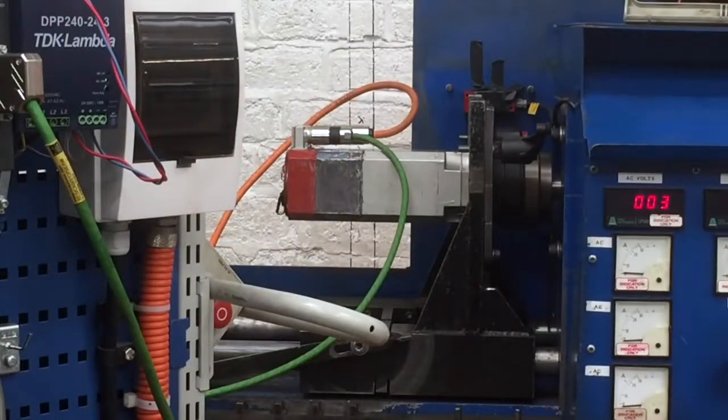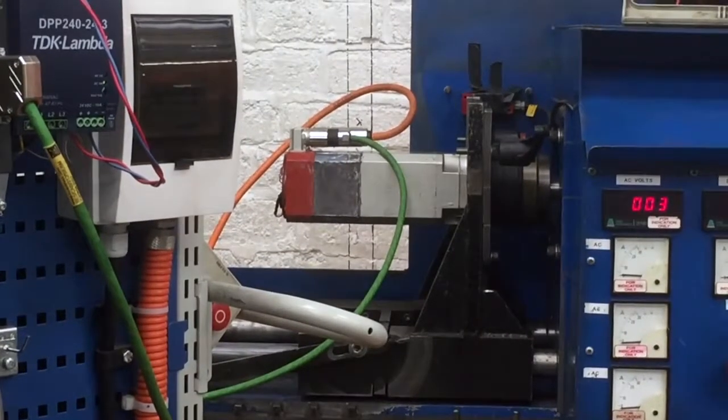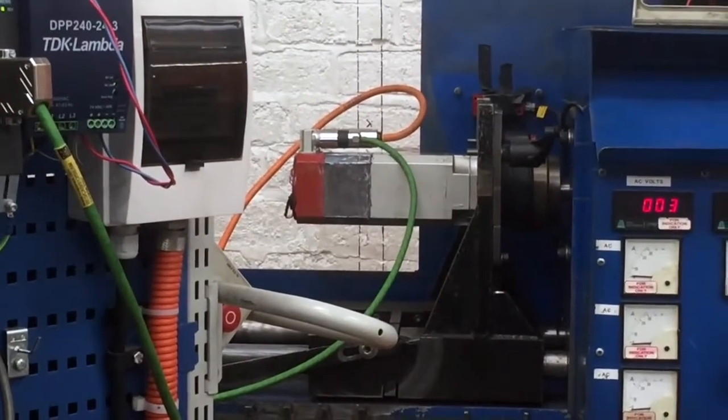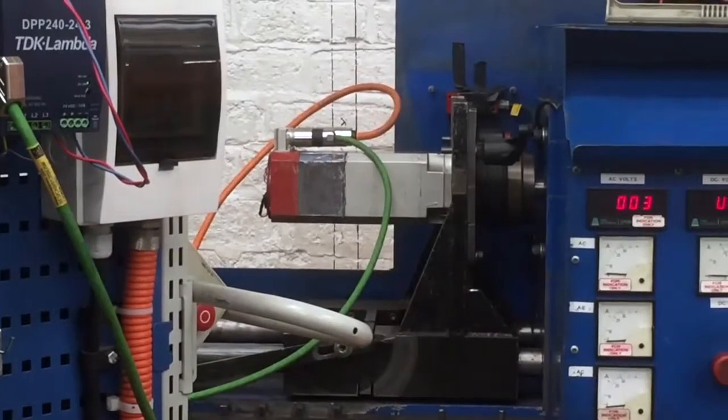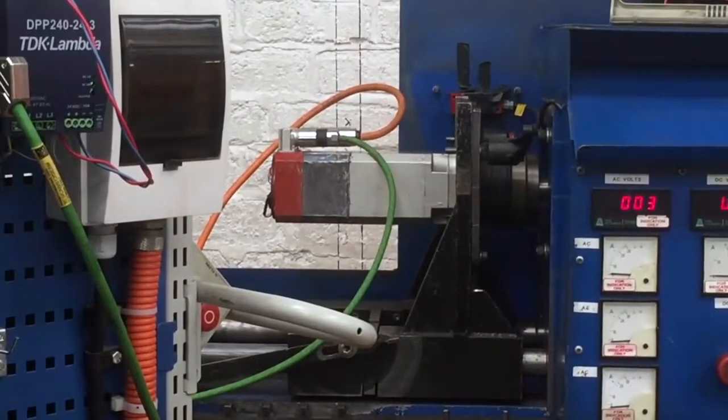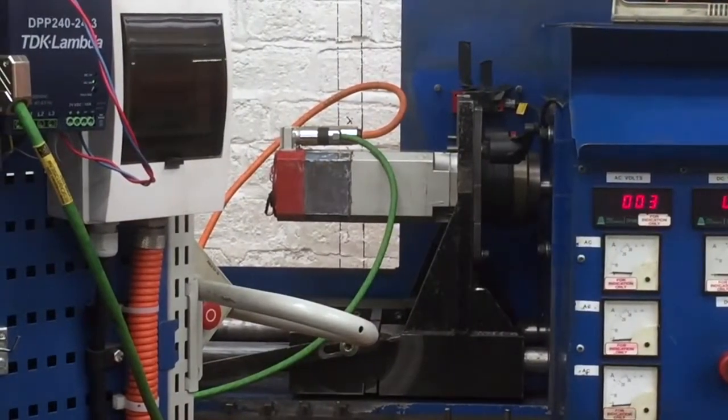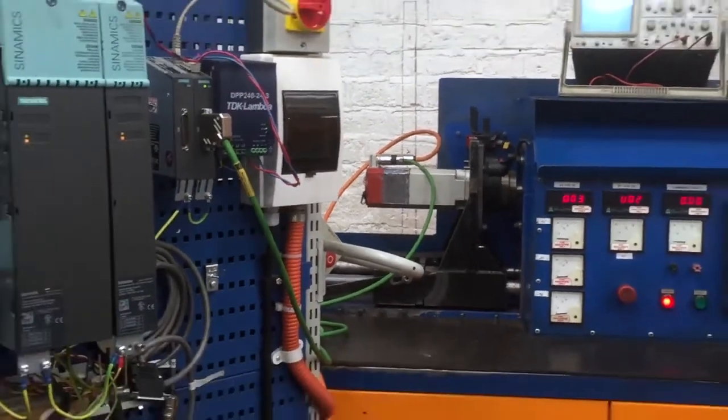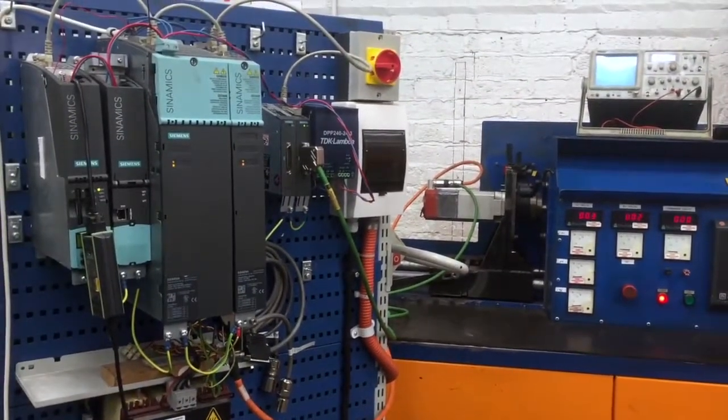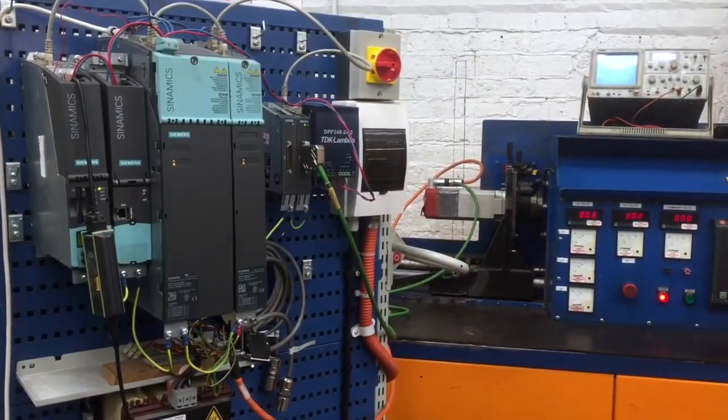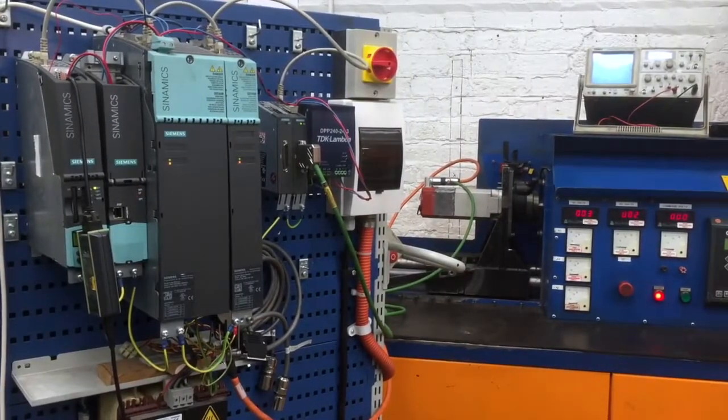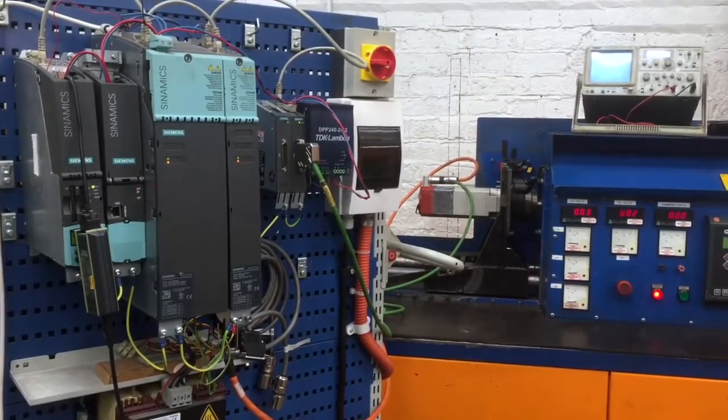We are now performing the first test on the motor, which is a no load test to check for the motor operation. As you can see, the motor is rotating, the coupling into our test rig. The drive system we use for Siemens servomotors is the S120 Sinamics range. This will give us the ability to test all Siemens range of servomotors.